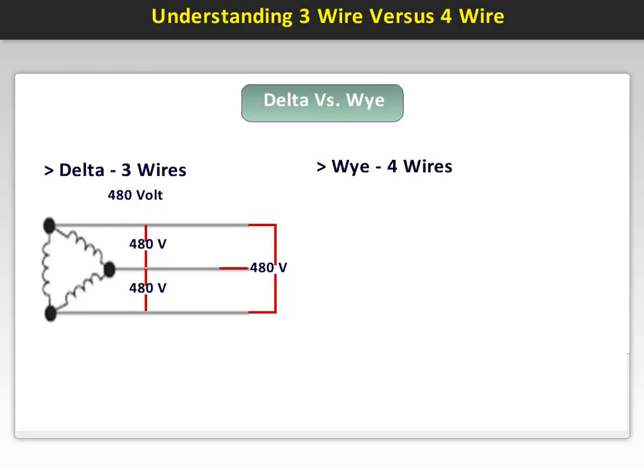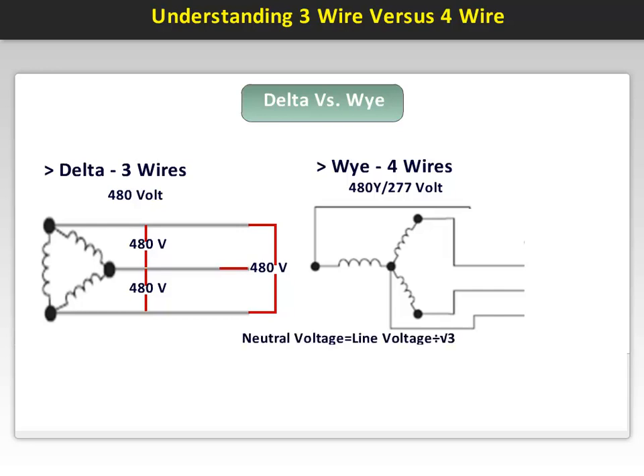Four-wire voltage sources are usually Y configurations, as seen here. This example assumes a 480Y/277 volt four-wire source. We know that the neutral voltage is 277 because the formula seen here states that the line voltage divided by the square root of three determines the neutral voltage. In our case, 480 volts divided by the square root of three calculates the 277 volts.